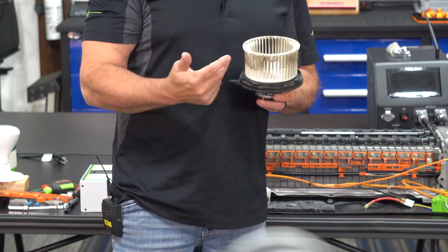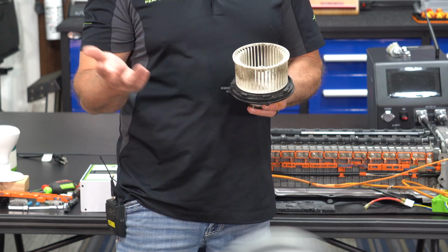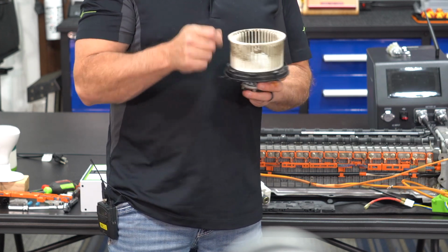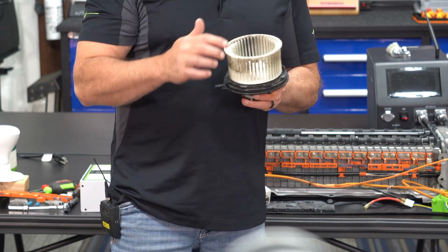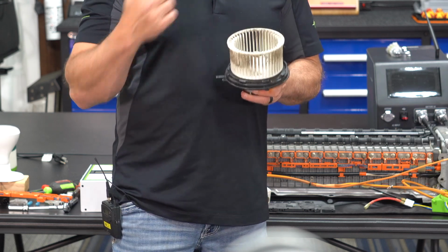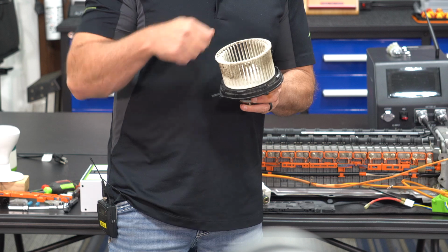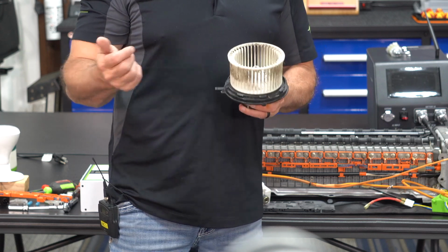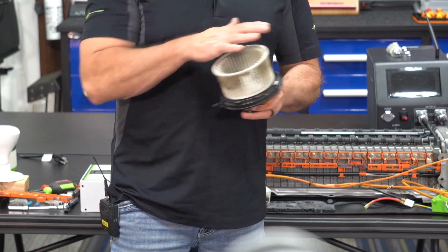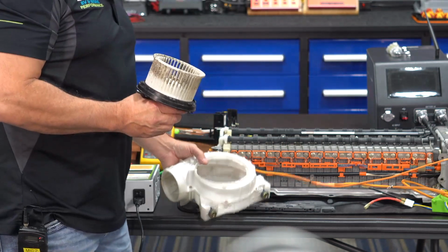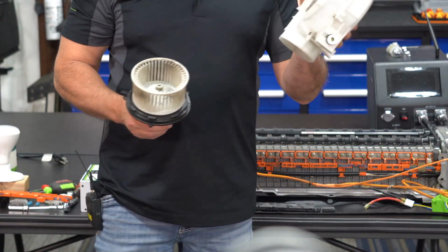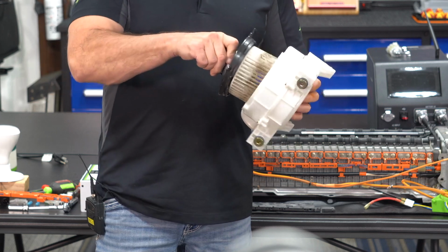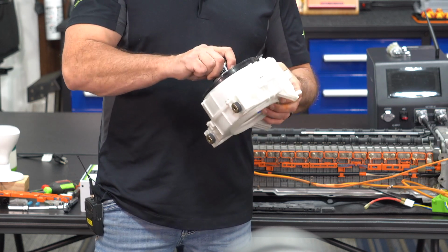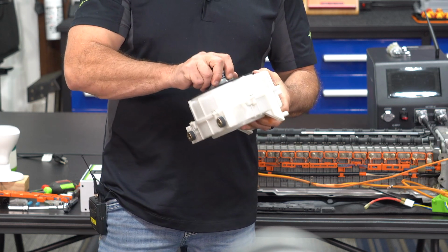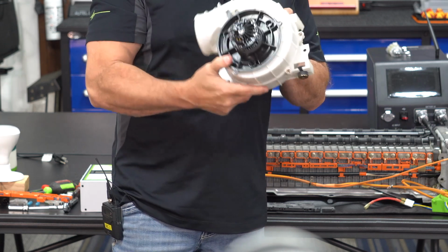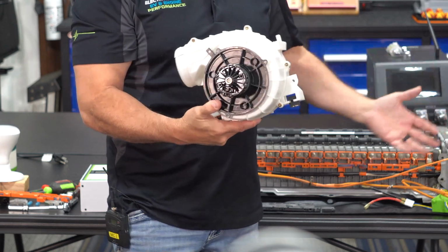So to service this, I actually have a little toothbrush that I use. I'd go ahead and clean out all those little squirrel cage fins there. I'd take a compressed air blowgun and blow that all off. If it's really bad, you might even want to use some Simple Green on it. Make this all clean. Also make sure that the squirrel cage housing is all cleaned out as well. Once you did that, you would have to start with this procedure first if it has a blower motor, because you're going to need this fan in the process of balancing the battery.